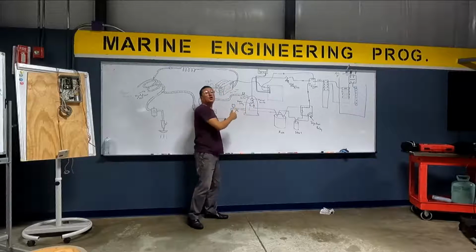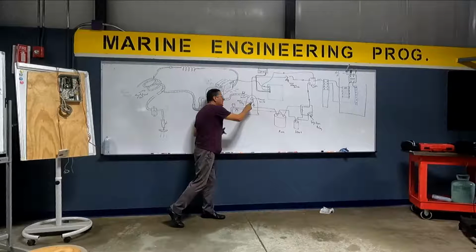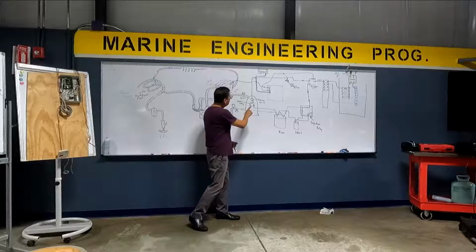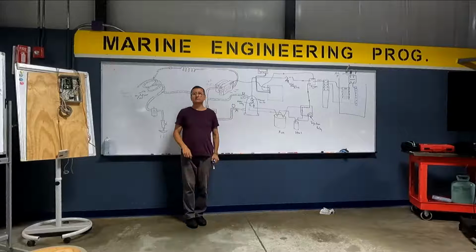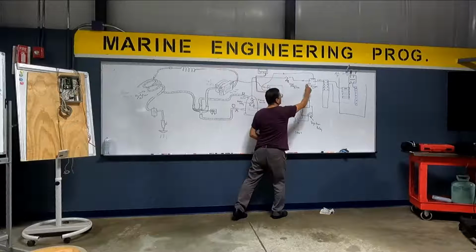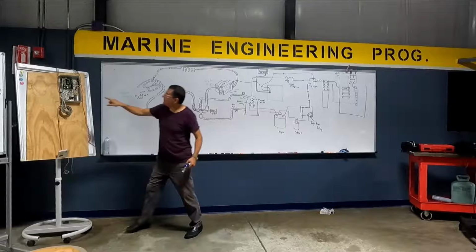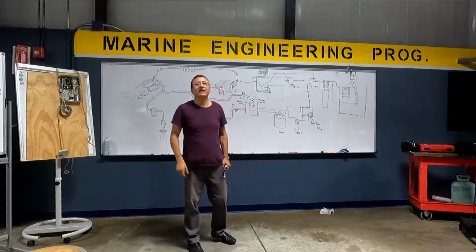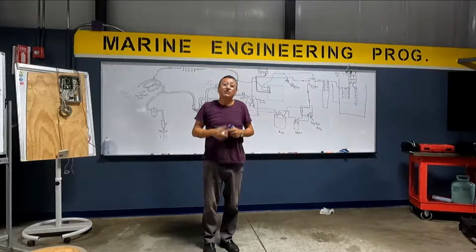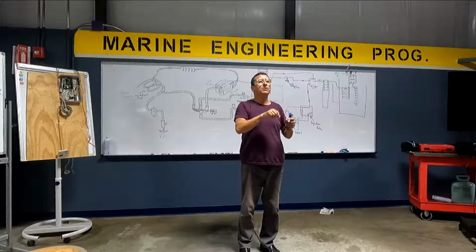This is the motor relay or compressor relay. Follow me? This is the motor relay or compressor relay, and now I have power in the middle of the relay, in the top one. I don't have power here and I don't have power here. At the same time, the relay sends current here and also sends current to this relay. This small block is the system relay. System relay is the relay of the complete system, the entire system. It's another relay. We have two relays. One relay in the motor of the compressor and another relay in the control box for the system.